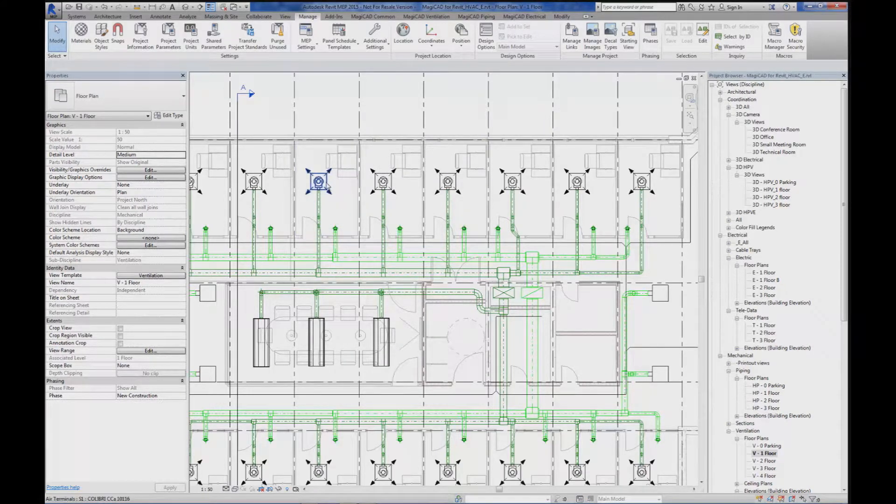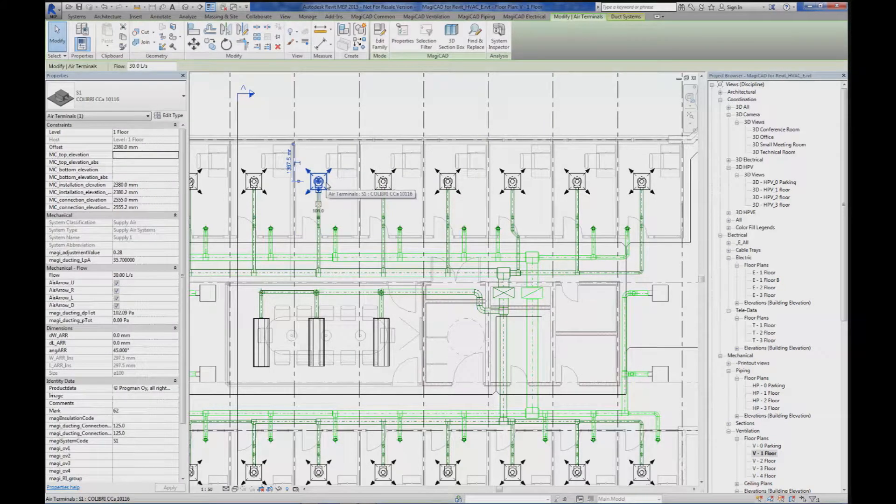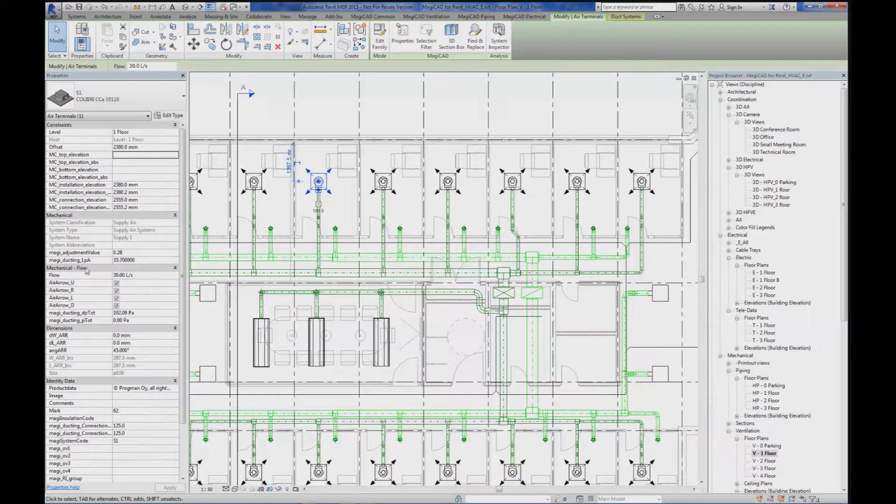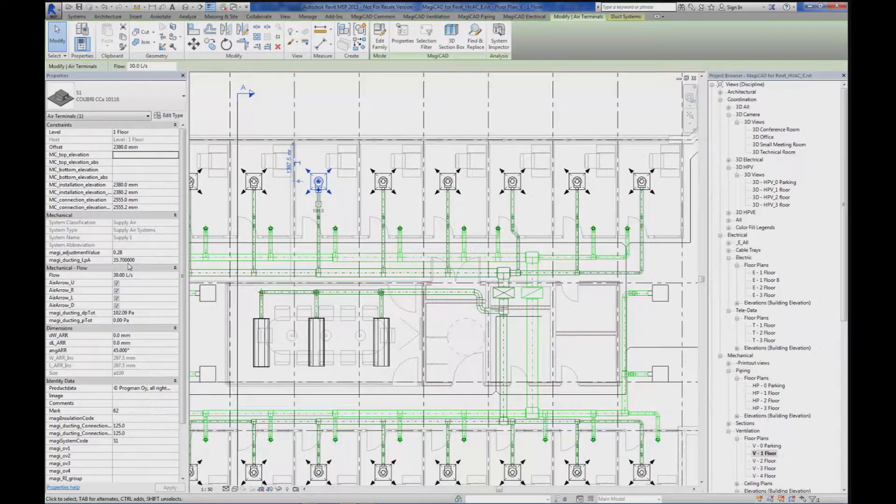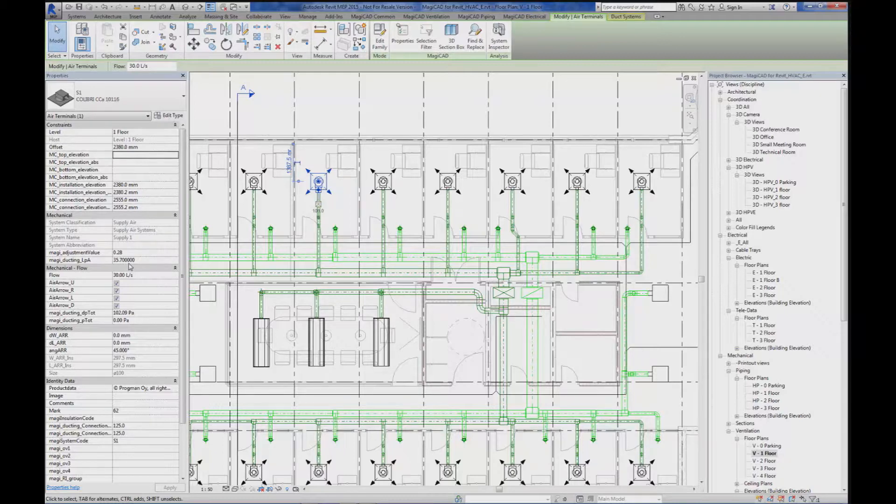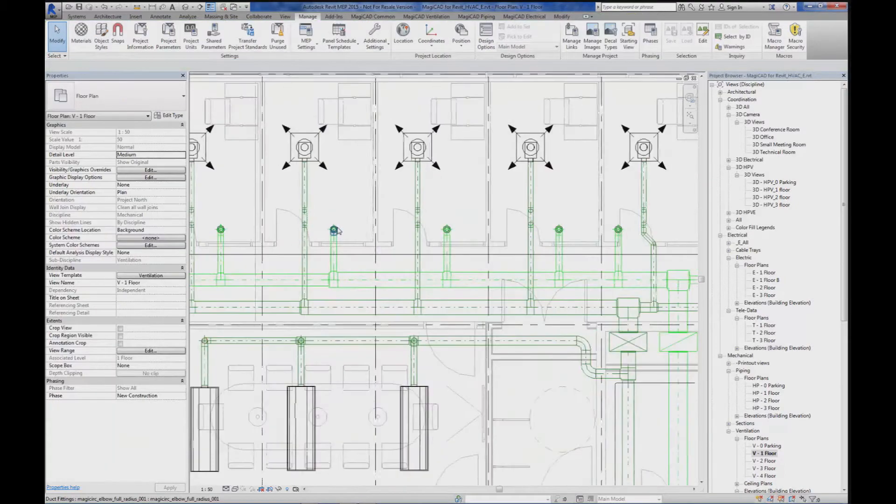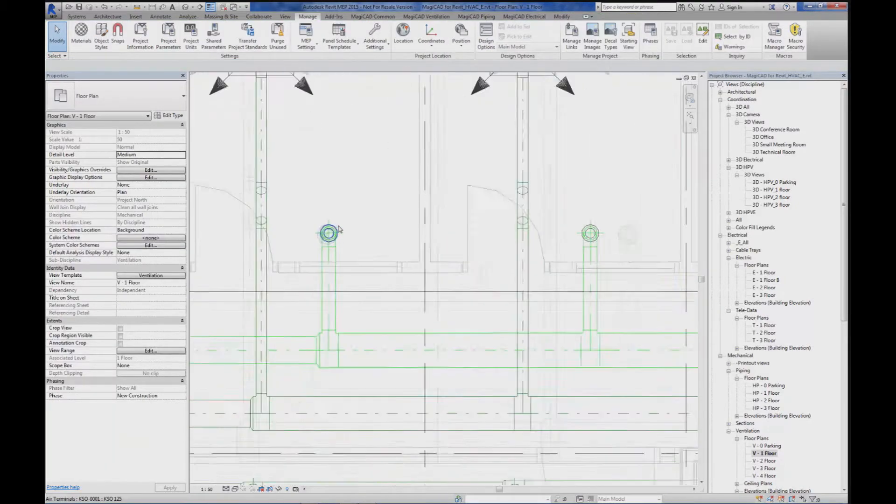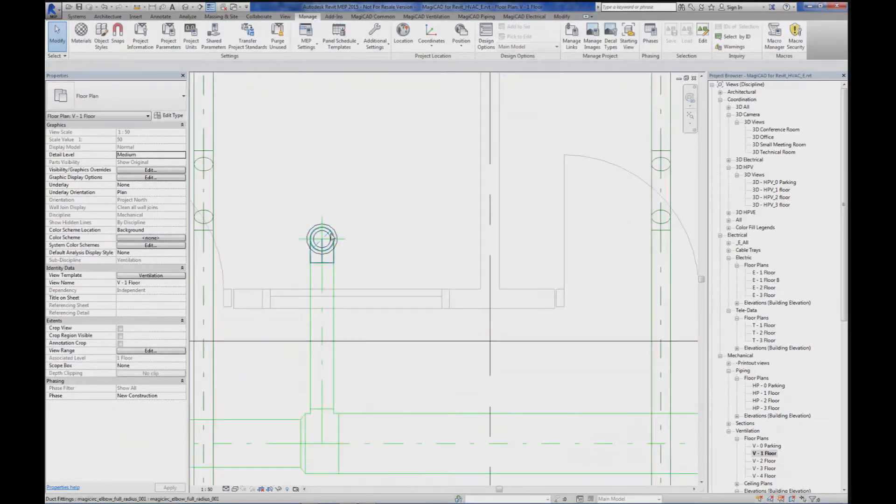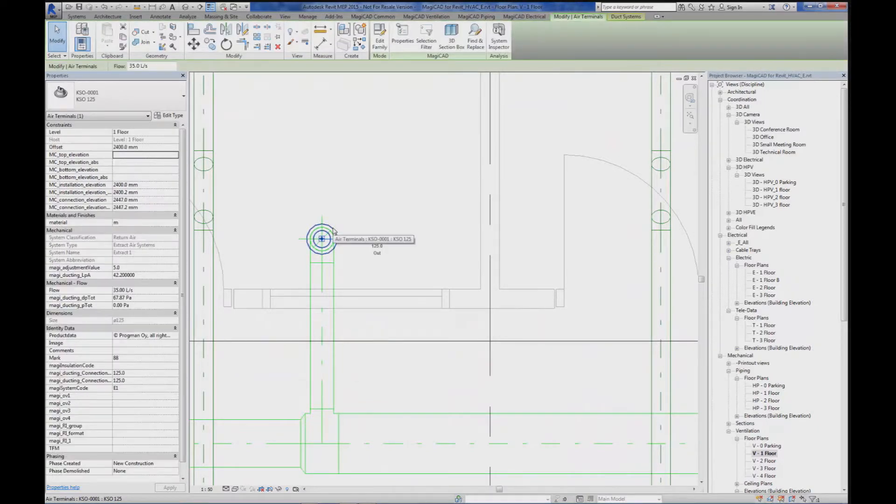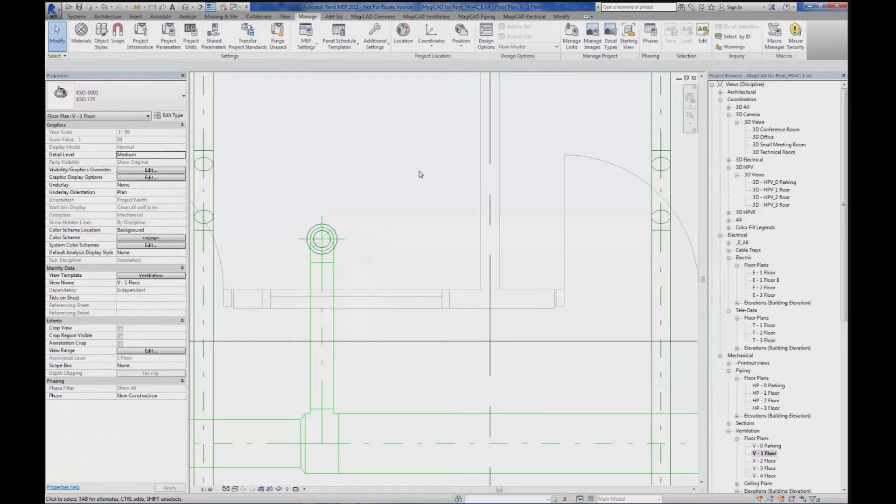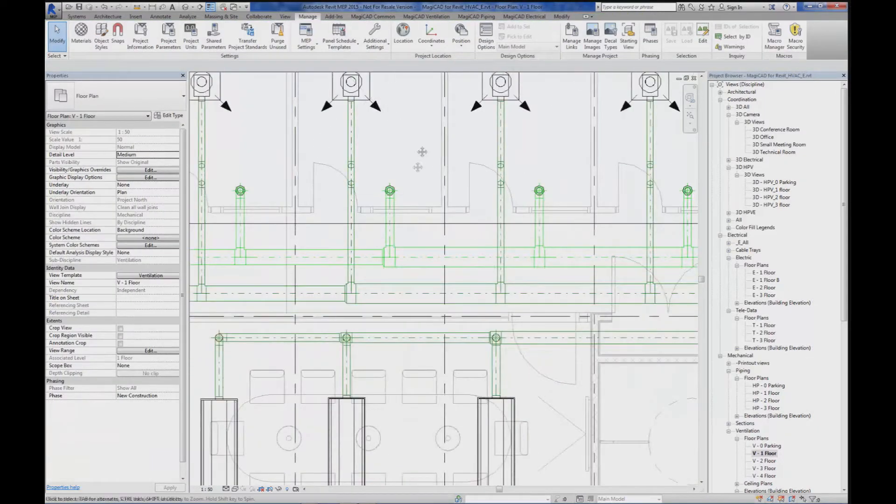If you look at the air terminal, we can see that we have a LPA calculated sound level coming from the system after we were running the sound calculation of the system. The same is for the extract air terminal. 42 dBA, which is quite high.